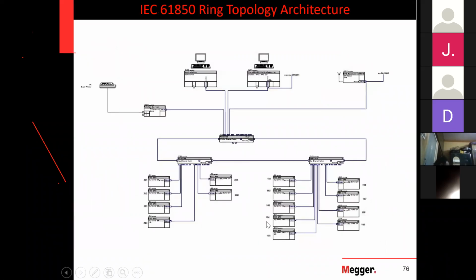This is the architecture. So let us very clearly understand this. The relays connected here. These are all the relays. Numerical relays. Fiber cable connected to the switch like this. This is, let us say, 230 kV side, 110 kV side. So from here, another fiber cable connected to another switch. From this switch, computer is connected. So this will have maybe RJ45 port to connect the computer, which has a printer and a GPS system, global positioning satellite, to time synchronize the equipments.